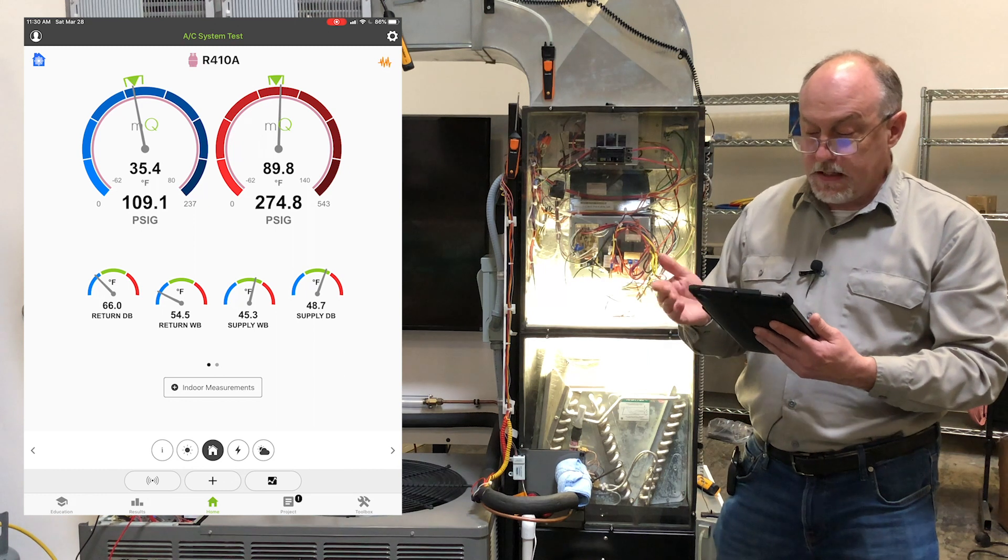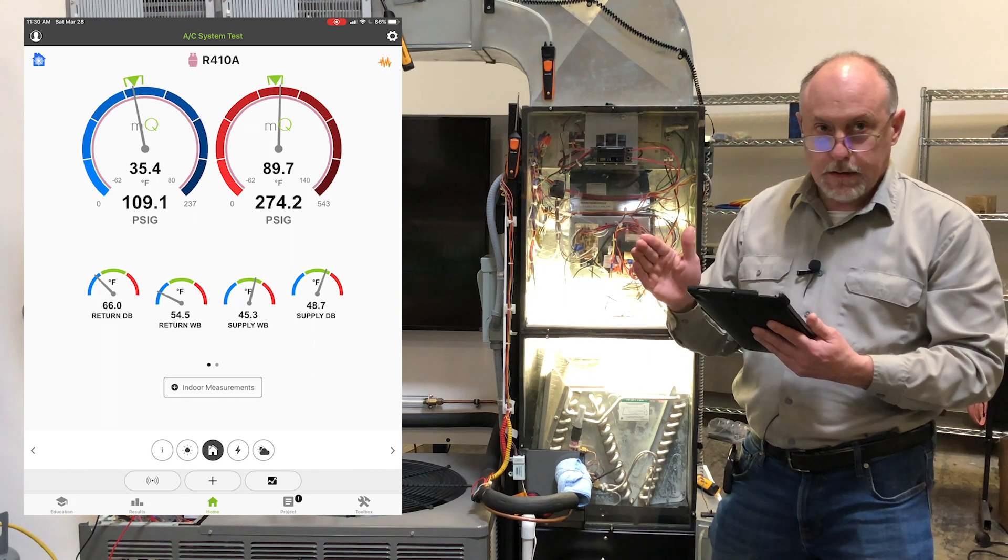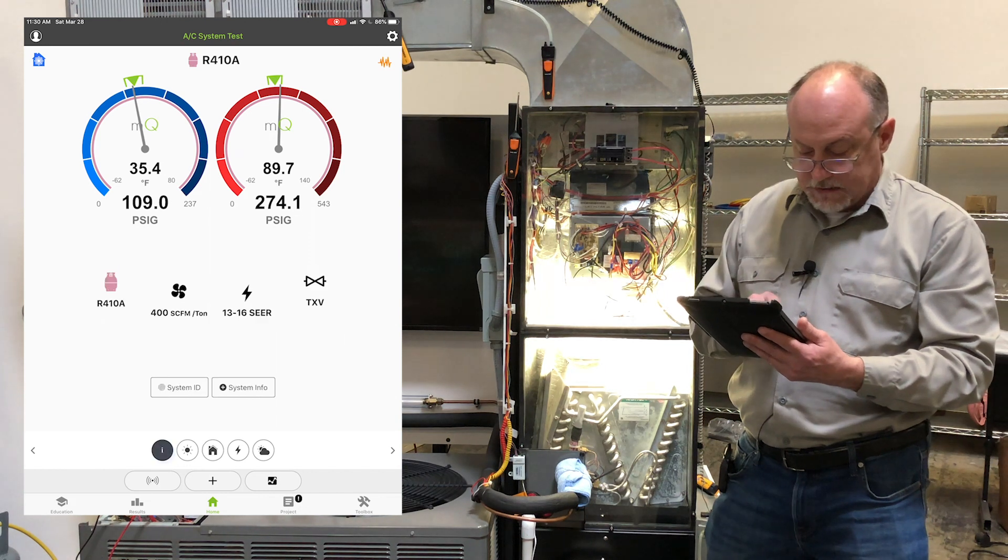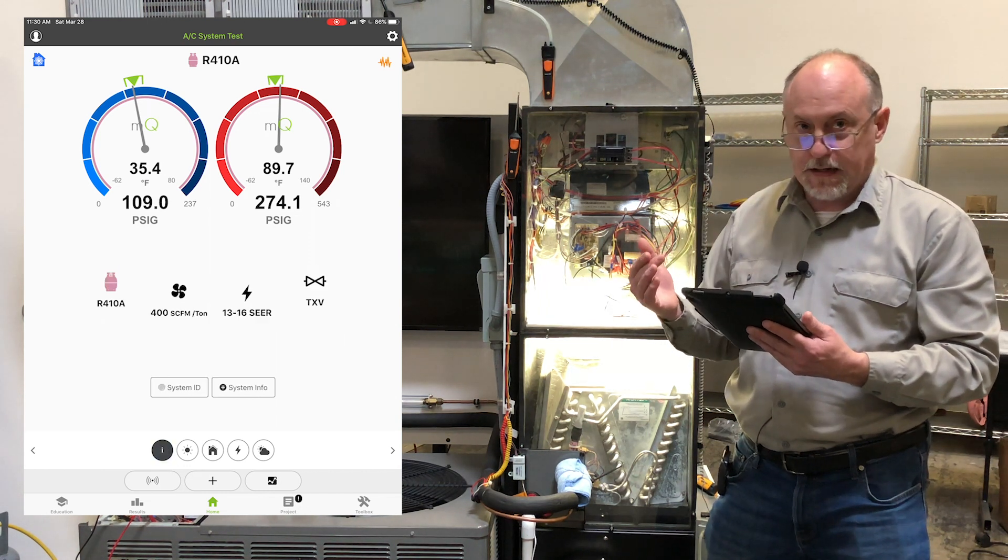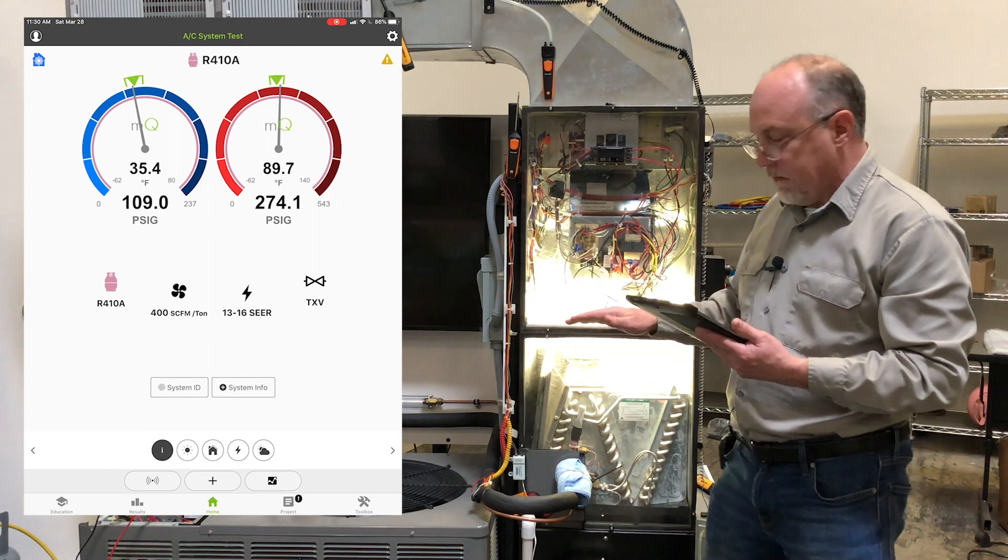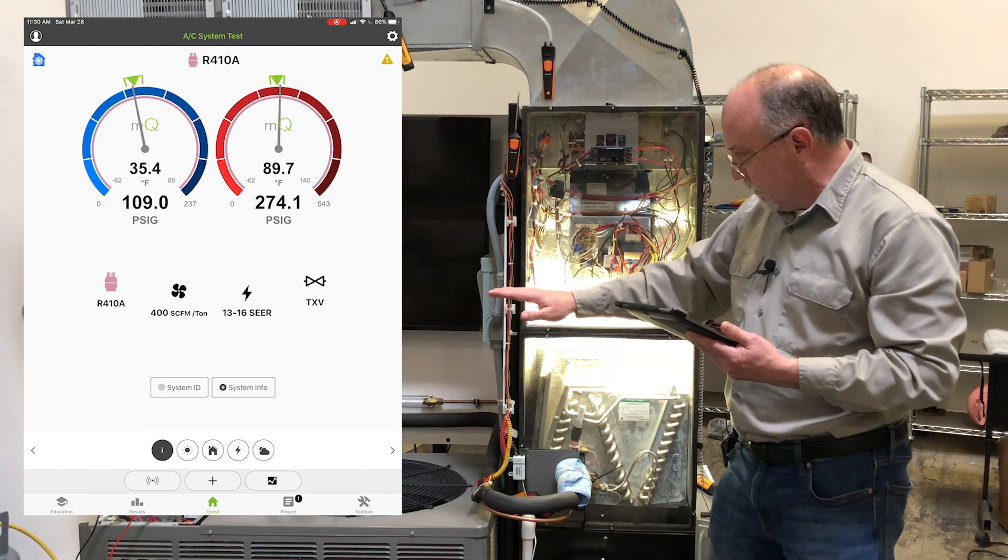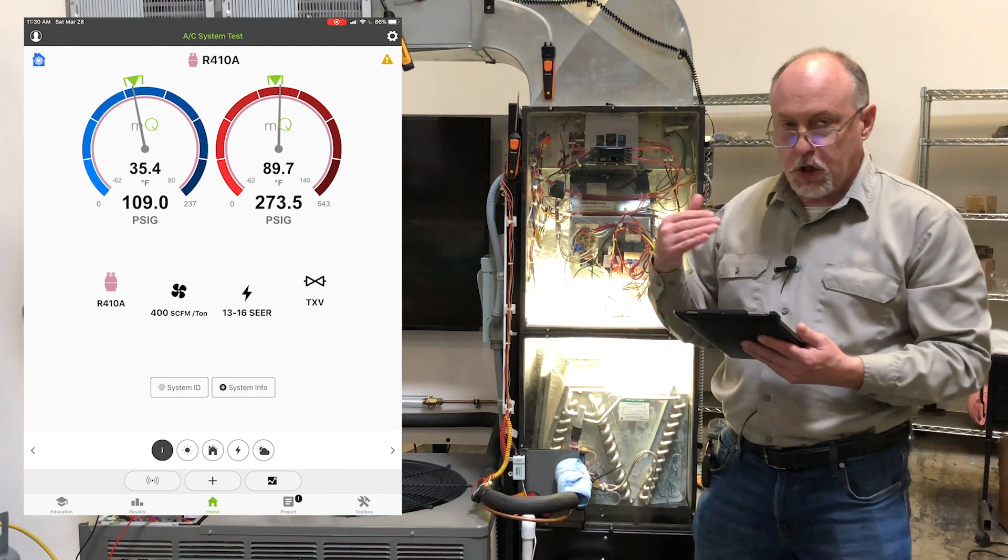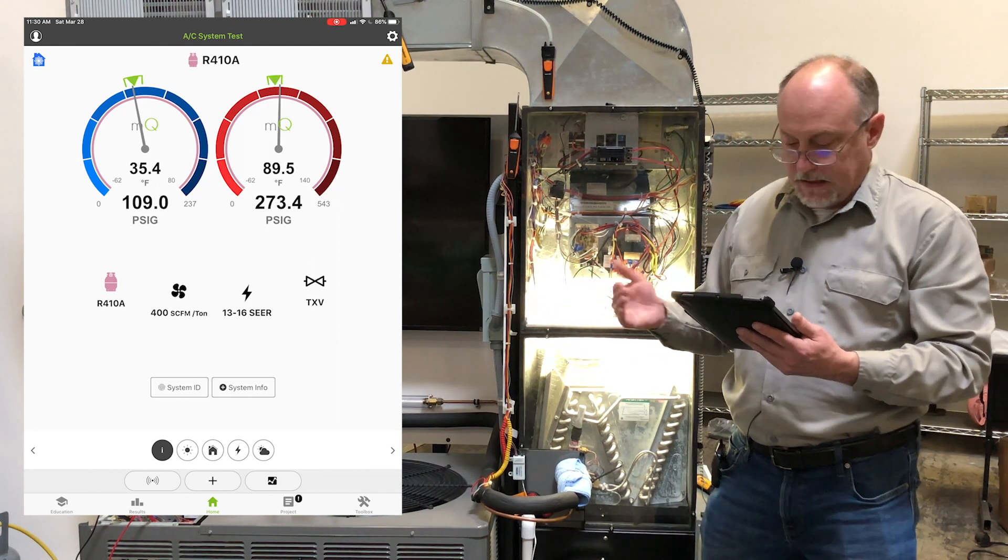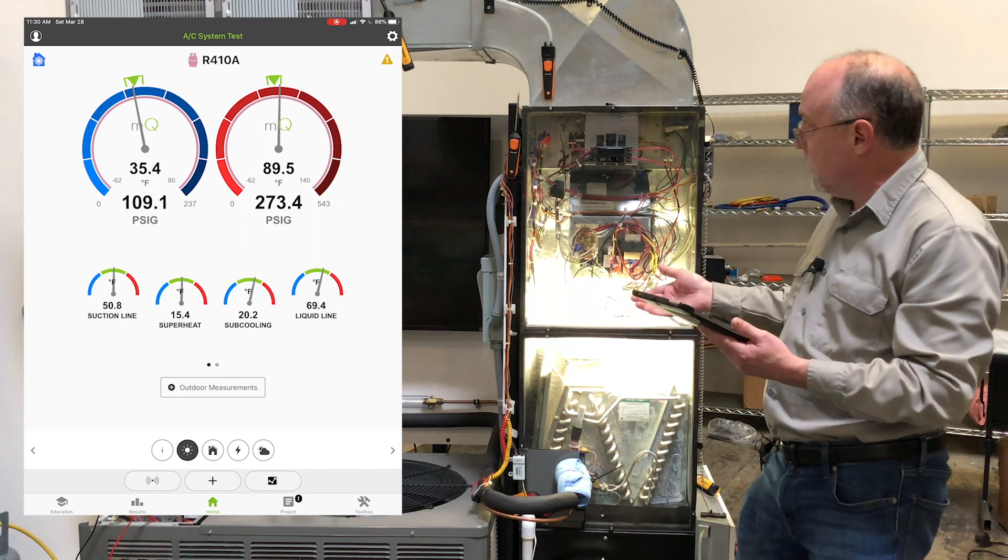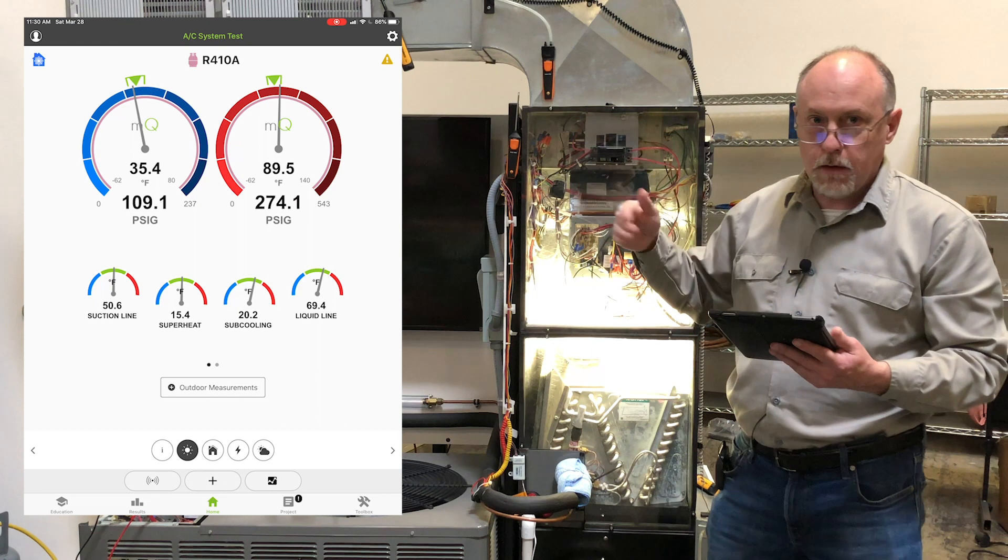And you can see there that the targets are close. But this initial profile is just a guess. We actually have to take into account all the installation variables of the system. So I have a line set of a certain length, a lift, the charge that I put in it. And so it calls for 19 degrees of subcooling. I'm actually at 20 degrees of subcooling. I have the duct system that's attached to it and the airflow.